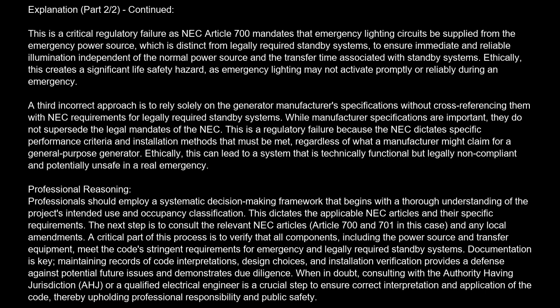A third incorrect approach is to rely solely on the generator manufacturer's specifications without cross-referencing them with NEC requirements for legally required standby systems. While manufacturer specifications are important, they do not supersede the legal mandates of the NEC. This is a regulatory failure because the NEC dictates specific performance criteria and installation methods that must be met, regardless of what a manufacturer might claim for a general-purpose generator. Ethically, this can lead to a system that is technically functional but legally non-compliant and potentially unsafe in a real emergency.